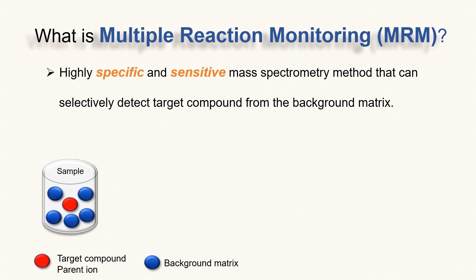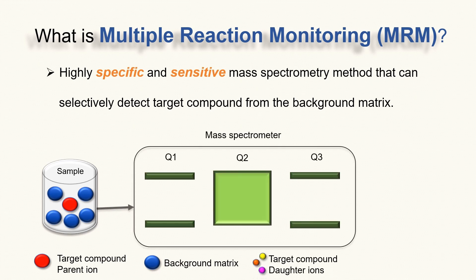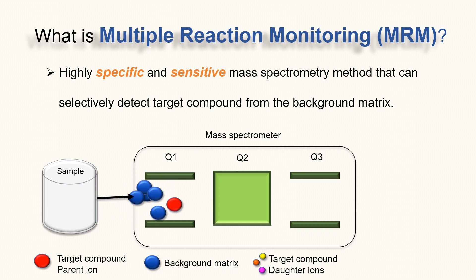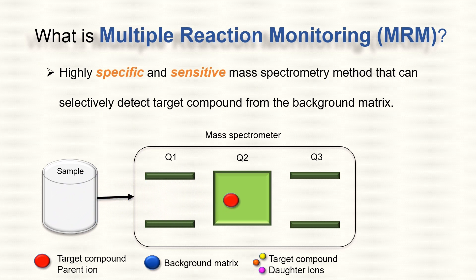The red ball represents the parent ion of your target compound; the blue balls represent background matrix. When the sample enters the mass spectrometer, both the target ion and background matrix enter Q1. Q1 is set in a way that only the target ion can travel through Q1 into Q2.